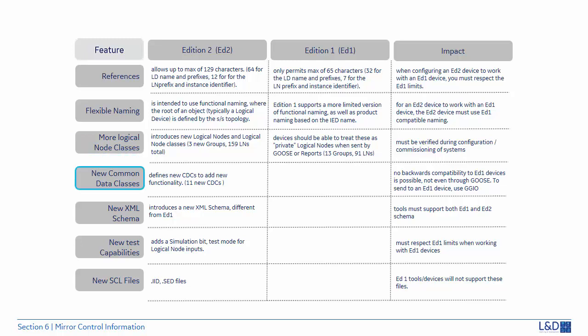New common data classes were added in Edition 2, which are not backwards compatible with Edition 1 and require the use of GGIO mapping. There's a new expanded XML schema in Edition 2. So when viewing or creating schema, you need to make sure that the application you're using supports both Edition 1 and Edition 2 schemas. New test capabilities were added to Edition 2 in the form of a simulation bit and test mode for the logical nodes, which Edition 1 does not support. And finally, in Edition 2, new substation configuration language files were introduced. First, the IID, the instantiated IED description file, and the SED, system exchange description file, which are not supported by Edition 1.